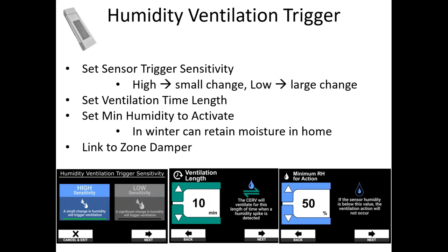You then set a ventilation time length. So it's not just going to run to bring you down to a certain humidity level. That can get you into trouble depending on what's going on in the house. But this just lets you say, I want to ventilate for 30 minutes anytime it detects a change in humidity, an increase in humidity. So there is a termination to this ventilation.